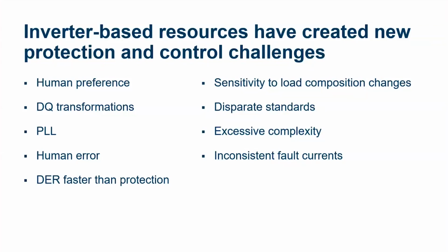Human mistakes, with thousands of settings and thousands of components that go wrong, a small human mistake can create problems with an IBR. Another challenge is that these DERs, especially inverter-based resources, can now act faster than some protection. They're sensitive to different types of loads. The load of a data center is very different behaviorally than, let's say, the behavior of a mine or a rock crushing device. Very different load compositions can cause real problems with IBRs. The very standards we use to select inverter-based resources can also create a challenge itself.